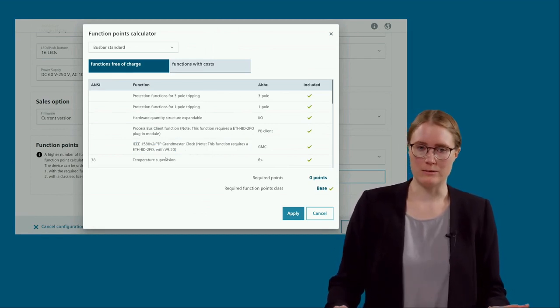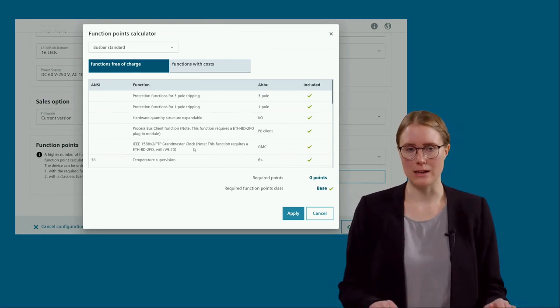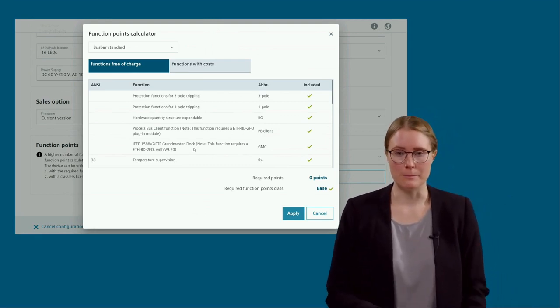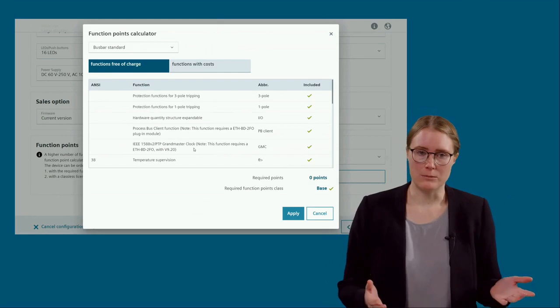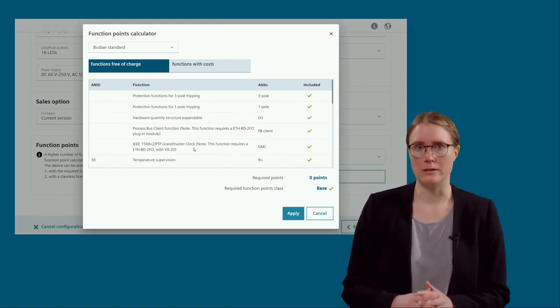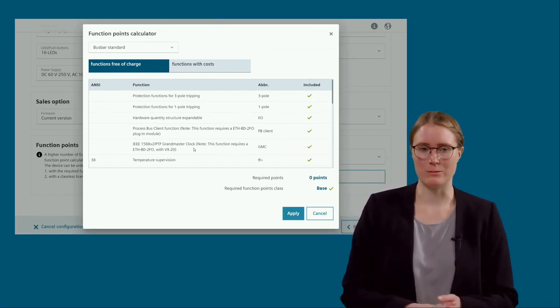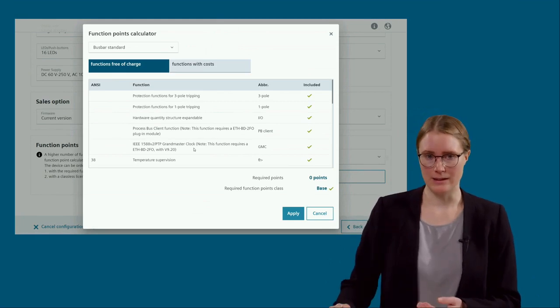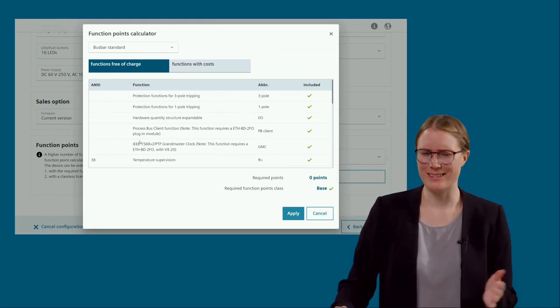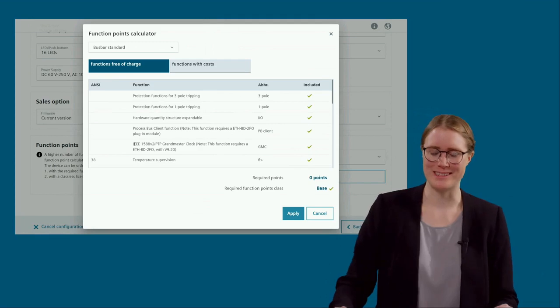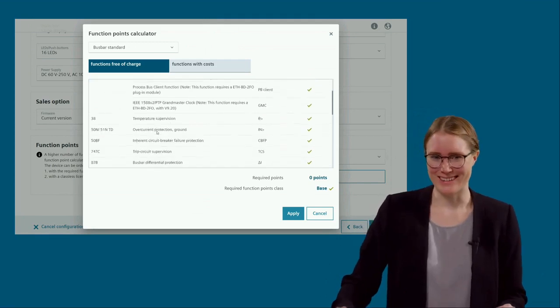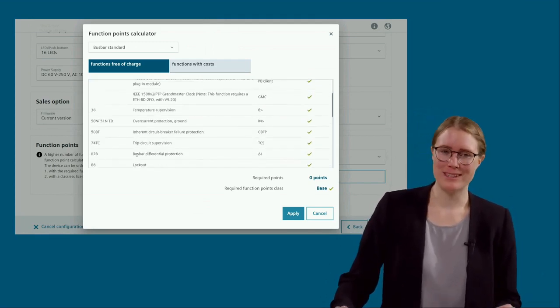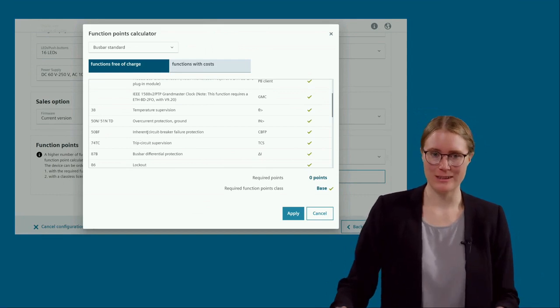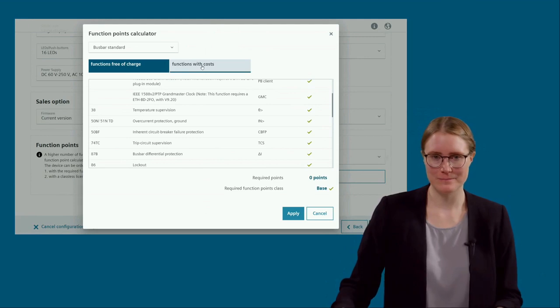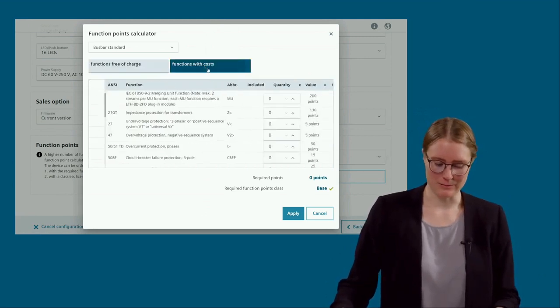And if you activate the Grandmaster Clock in the 7SS85, no additional switches, for example, with a Grandmaster Clock included, or no additional Grandmaster Clock would then be necessary. And it doesn't even cost any function points here. Okay, and of course the busbar differential and the inherent circuit breaker failure protection are also included, same as before. So I go to the function with costs now.